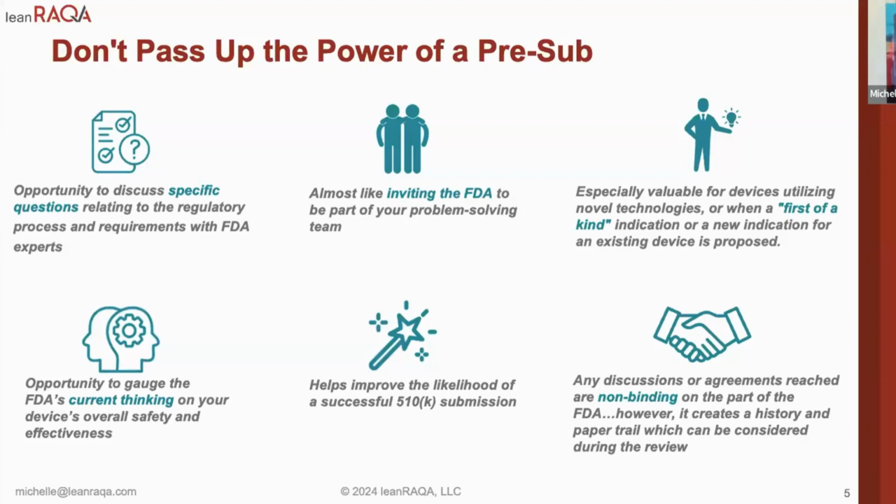It's also important to know that these are technically non-binding, but the FDA does intend to honor their opinion if their current thinking has not changed between your pre-sub and your submission. Most importantly, it is still free. It's free, and they're pretty good about hitting their timelines. So there's really nothing lost by doing your pre-submission.